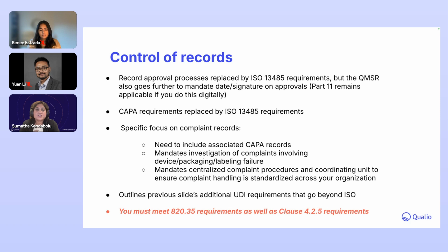CAPA, that is the corrective and preventive action requirements, are replaced by ISO 13485 requirements, with a specific focus on complaint records. You need to include associated CAPA records, and mandate investigation for complaints which are specifically about the device, packaging, and labeling failures. It also mandates centralized complaint procedures and a coordinating unit to ensure complaint handling is standardized across your organization. As outlined in previous slides, there are additional UDI requirements that go beyond ISO. So you must meet 21 CFR Part 820.35 requirements as well as ISO 13485 clause 4.2.5 requirements.